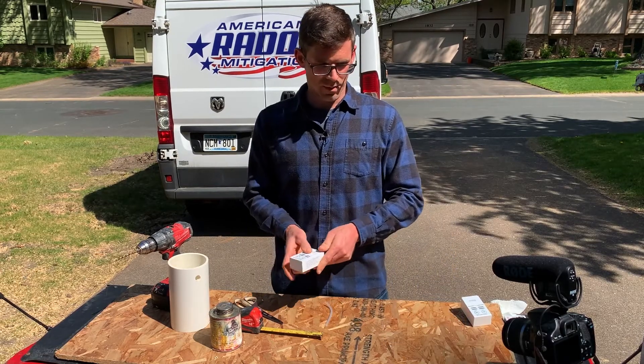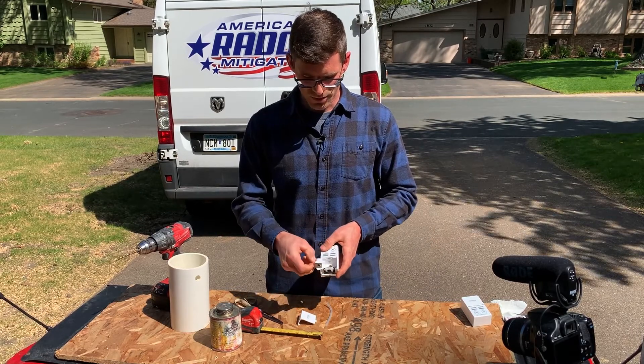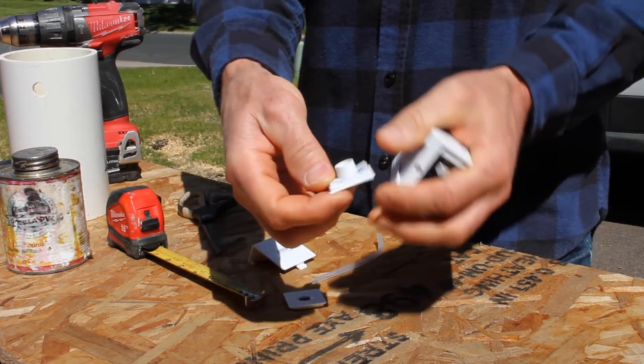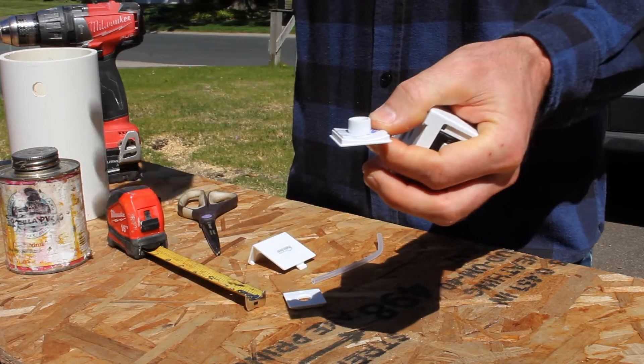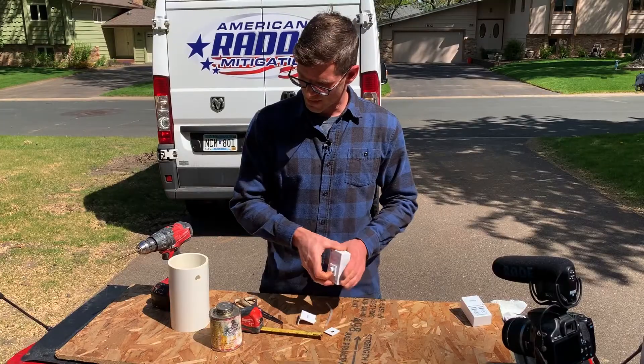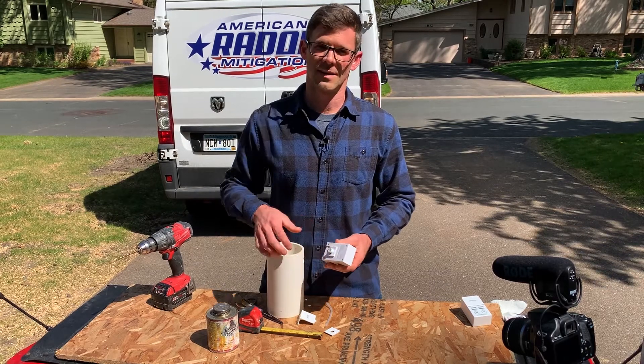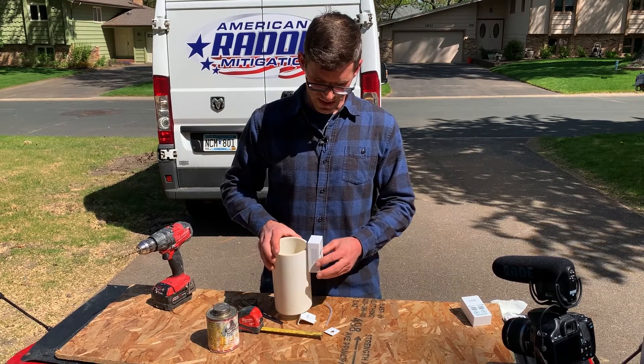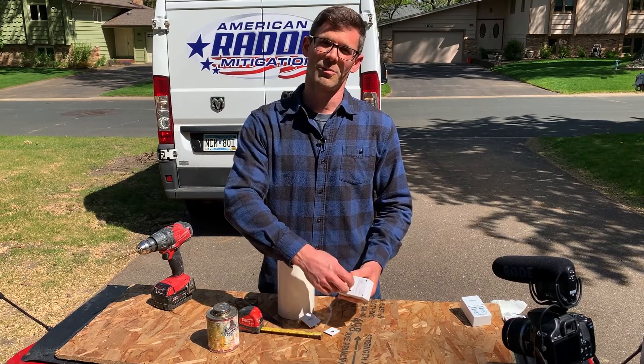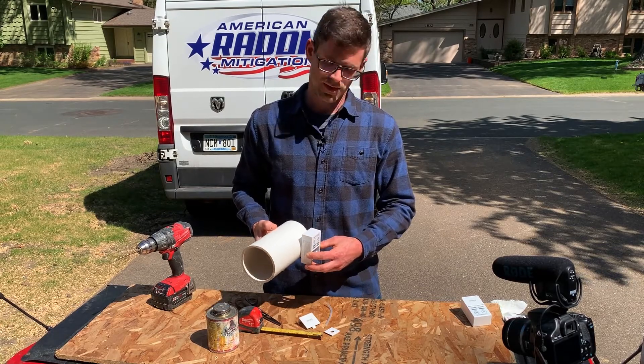It's designed to be mounted a few different ways. When we pull the cover off we've got two different mounting plates. One is convex — it's got that arch in it and can be mounted to a pipe. You drill a 5/8-inch hole in your pipe, and it's got some 3M sticky tape on it so you peel that off and mount it to the pipe. You can also put this mounting plate on the other way and mount it to a horizontal pipe.